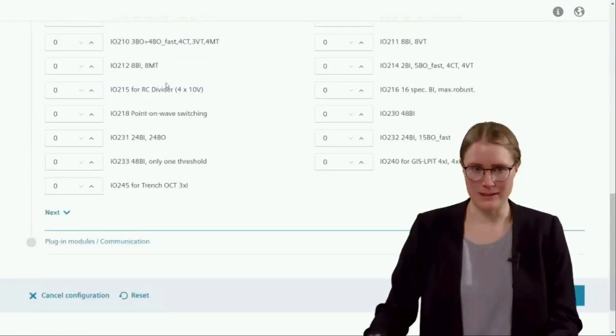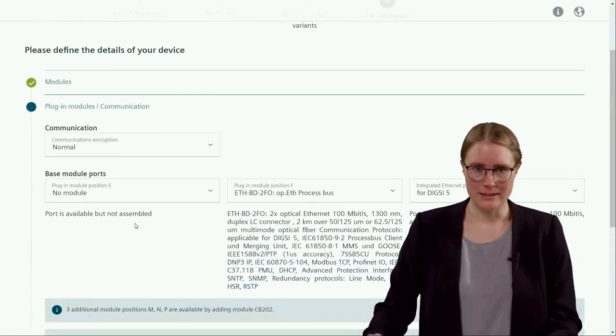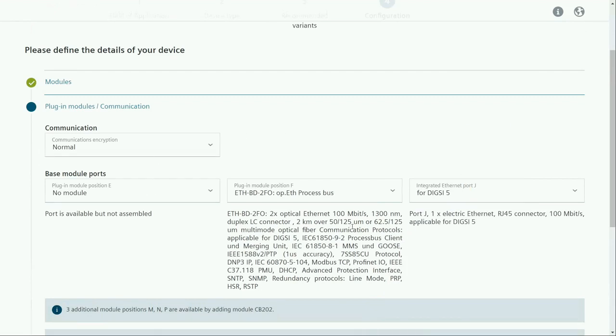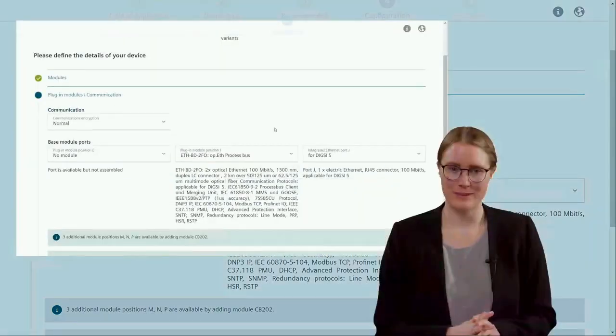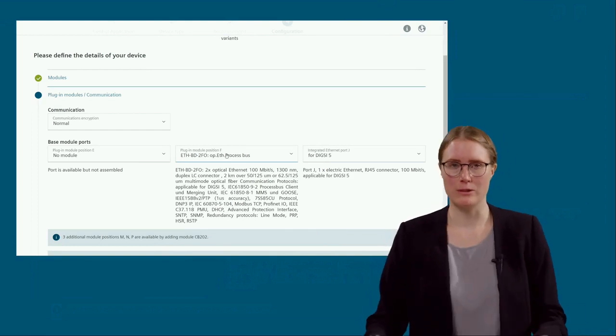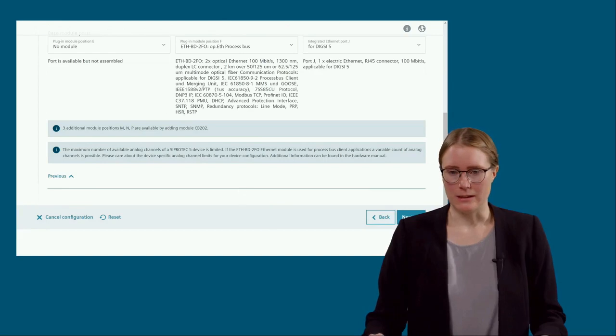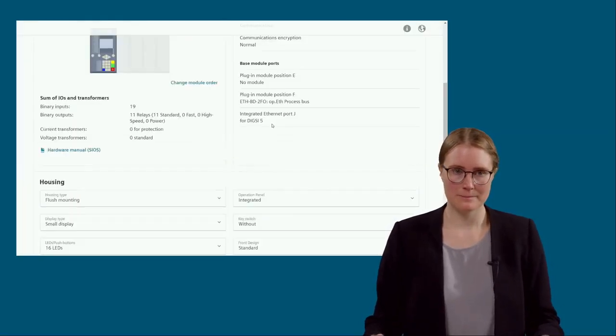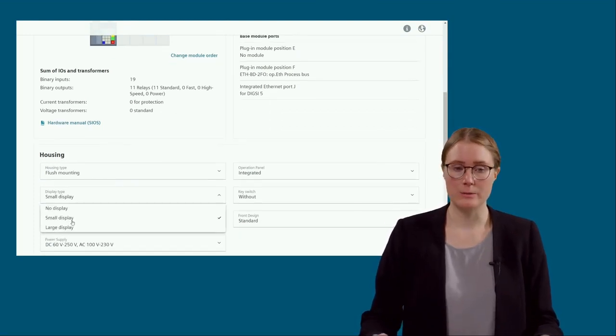So I could scroll down, go to next. And here you see an overview of the plug-in modules for communication. As you see, in the standard variant I chose, 1 Ethernet BD module is already available. And 1 Ethernet BD module is of course sufficient for our 5 bays. As we explained earlier, with 1 BD module you can cover up to 15 measuring points at the moment for the 7SS85 CU solution, and with version 9.40 it would be up to 16. So in this case, with our 5 bays, we are totally fine with 1 BD module. So I confirm this step and go to the next. Here, once again, I changed the display type to a large one.